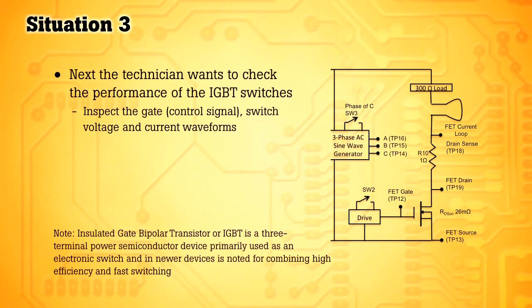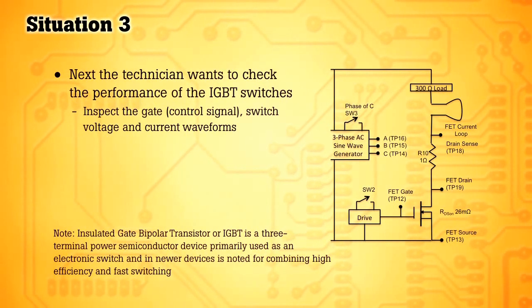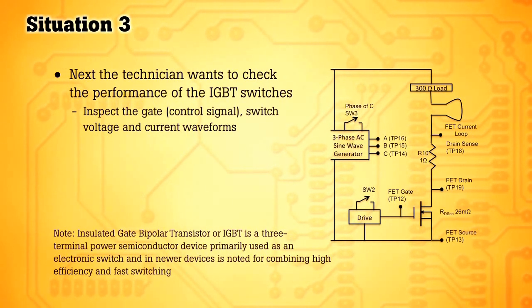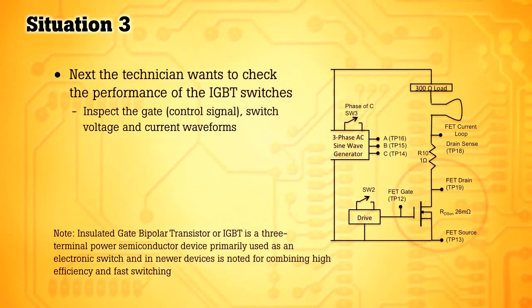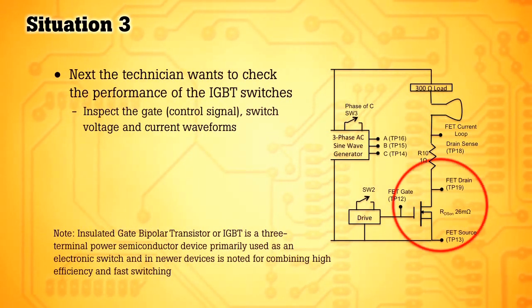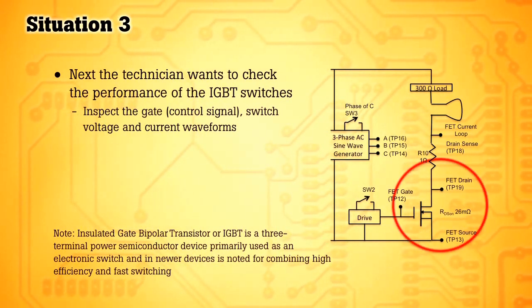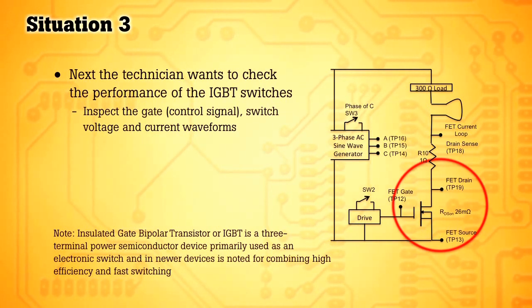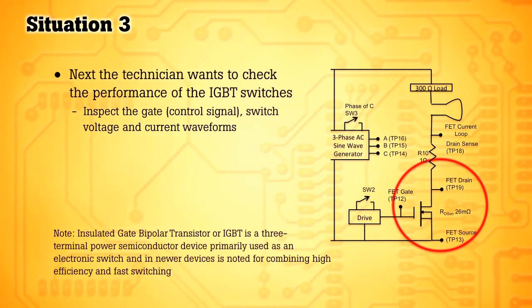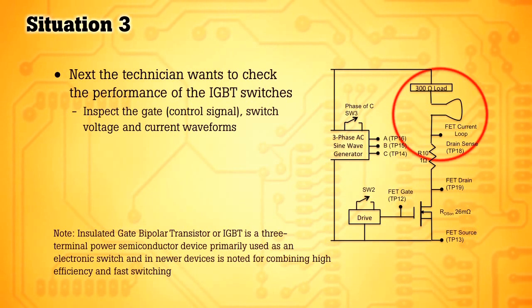So to inspect the switch, we're going to use the three input channels of the Scopemeter 190 Series 2 4-channel oscilloscope. The first channel will be looking at the switch control or drive signal. The second channel will look at the voltage output from the switch, and the third channel will look at the current through the circuit or the current through the circuit to the load.